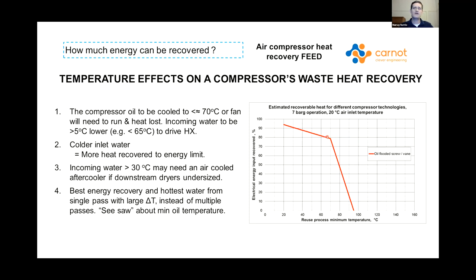Now, if that water is only heated 5 degrees, it's going to go out at 65 and you won't be able to use that water again to recover the rest of that heat. Whereas if you've got a 25 to 30 degree rise in that water, you can heat the water all the way up to the maximum it can do from that 65 degrees coming in. So it's really important to go with a single pass on your water, not lots and lots of little passes, but a single big temperature rise. Yes, you've got a low water flow, which can upset your coolers a bit, but it also reduces your pump power consumption, and you can go for smaller piping as well.